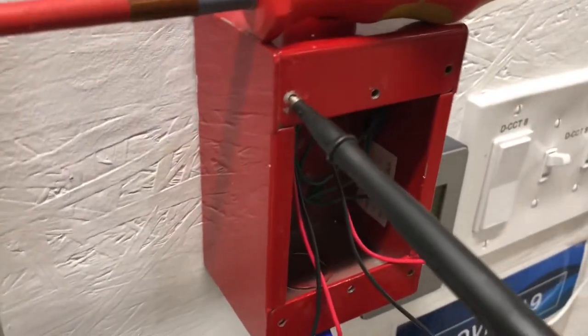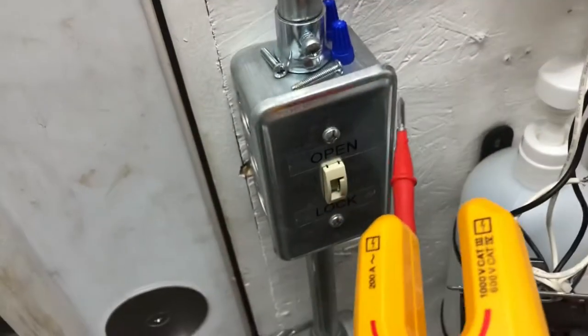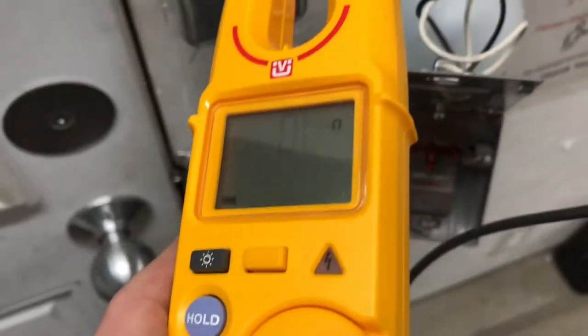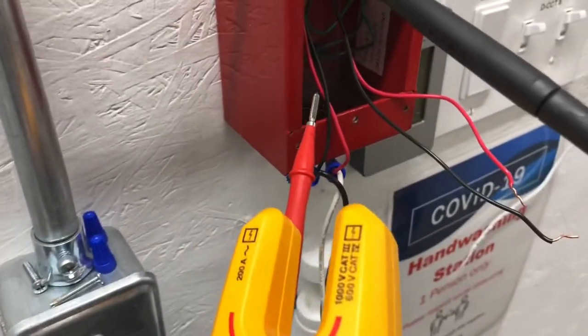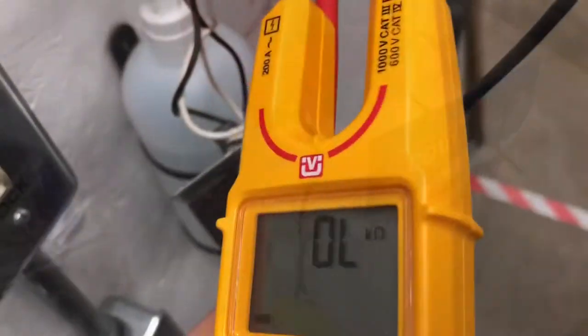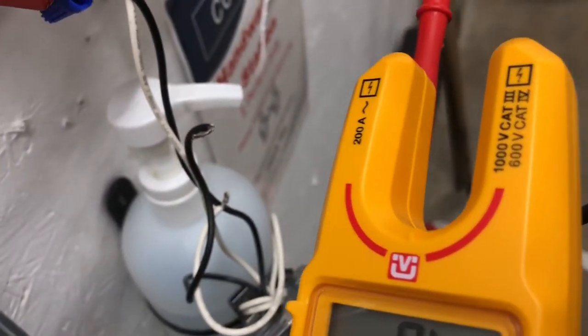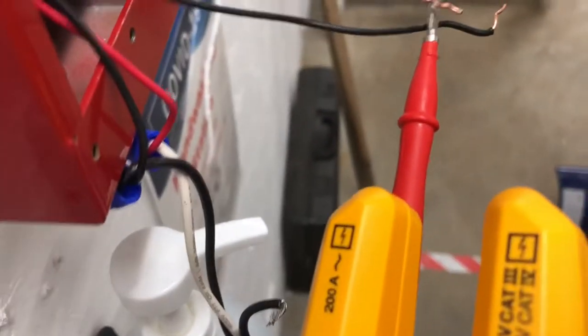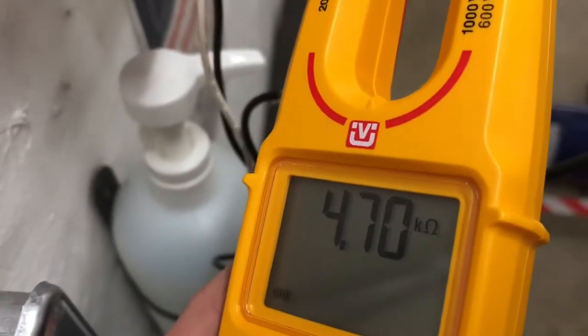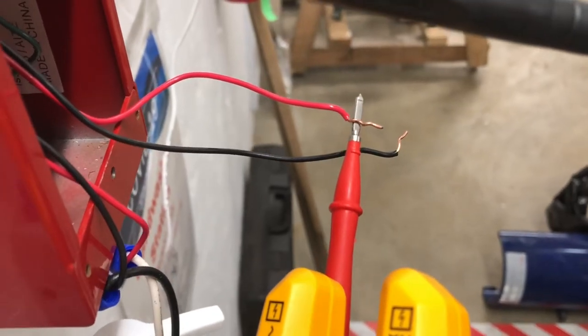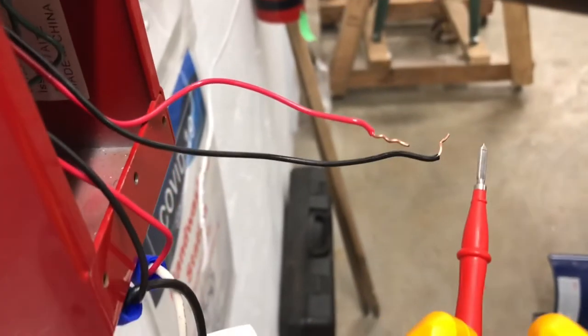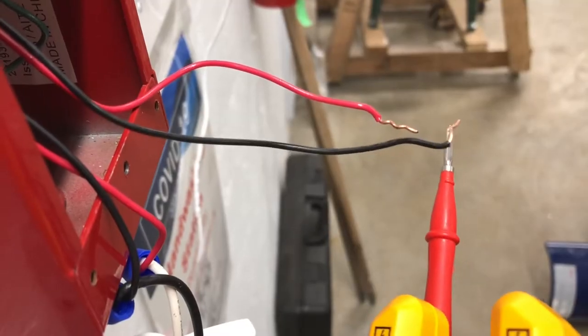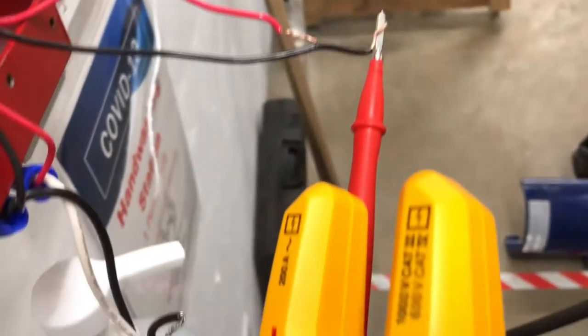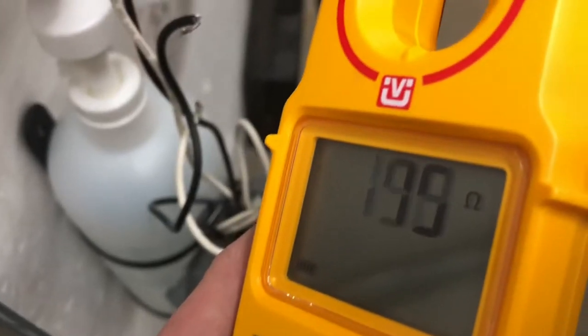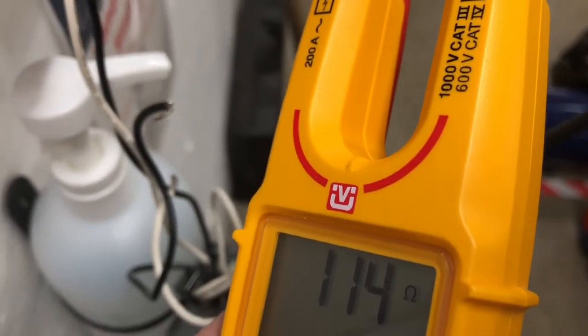At my first device here, I'm making a ground connection there. As you can see, if I touch it to something else grounded, I do have continuity, so we are grounded. We metered at the panel for continuity. On the positive, we got 4.7K, and as you can see from the outgoing on here, we still have around 4.7K, so we know it's somewhere going through the resistor, still going out from this point. And if we go on to our black, we can see we're still getting pretty low resistance, so we know it's on the negative somewhere past this device.